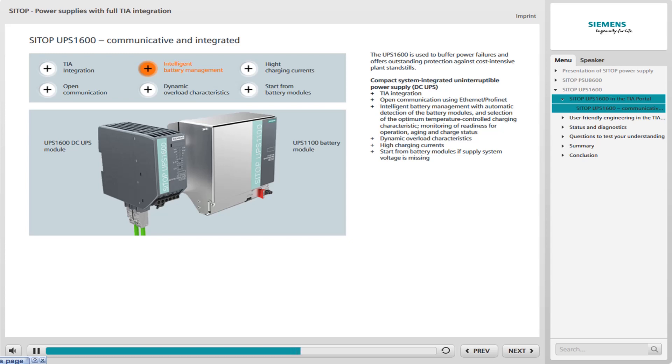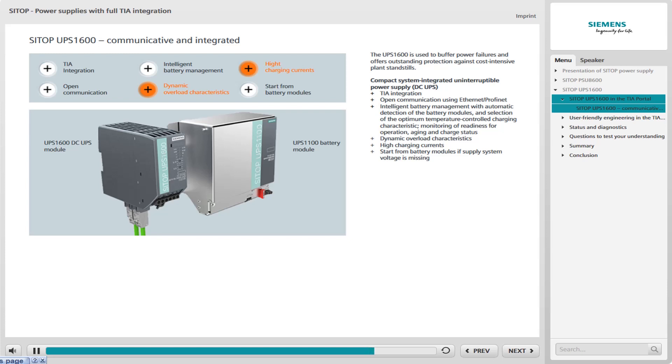The Ethernet-PROFINET interface is used to output the battery status and various up-to-date values such as voltage, current and residual capacity. The UPS 1600 has a dynamic overload characteristic and can thus also supply 24-volt loads with high inrush currents as well as industrial PCs. The high charging current for the battery modules quickly restores buffer readiness after a power failure. And for use in isolated operation, the UPS 1600 can be activated without input voltage with the help of the battery modules to enable machines to be powered up or switched on.